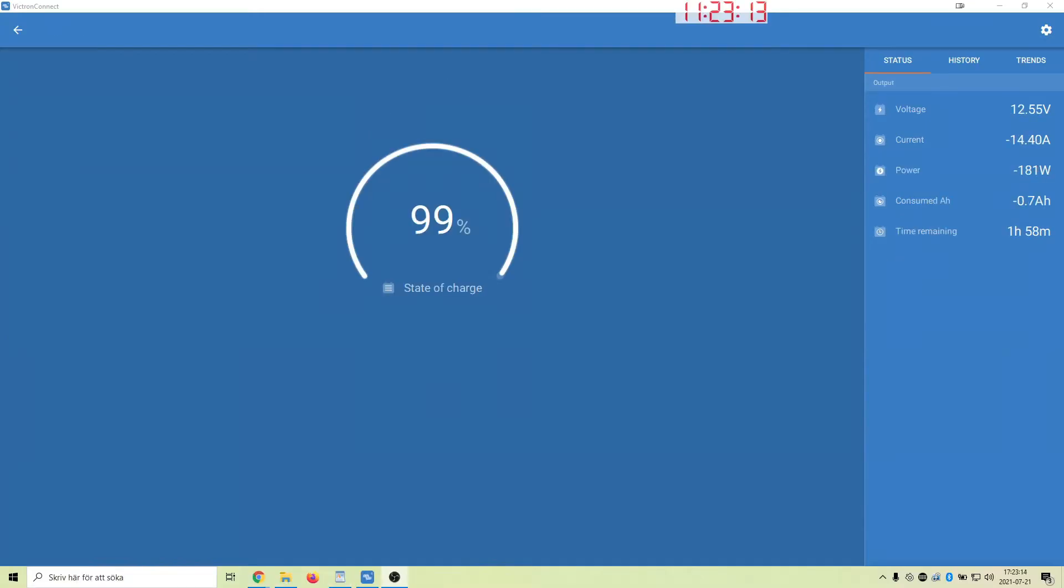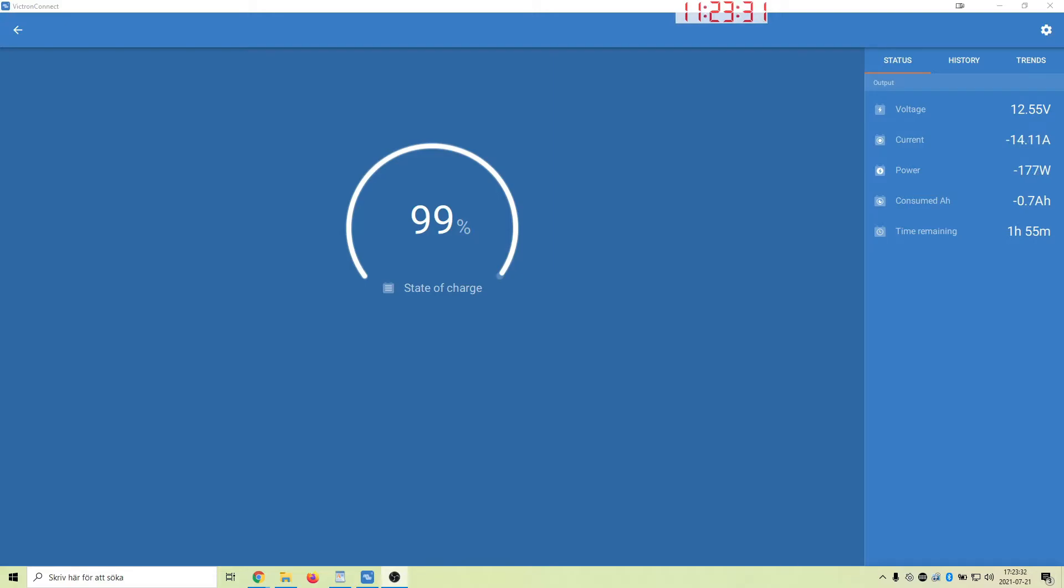Here you can see the readings from the shunt. I have connected the USB cable from the shunt directly to the PC and started the Victron app for PC. Right now it's pushing around 12 to 15 amps and that's my normal load. I've connected my laptop, a couple of monitors and also the Dometic fridge. Right now I have turned the solar panels upside down so they don't help. Also I have only one battery connected at this moment.